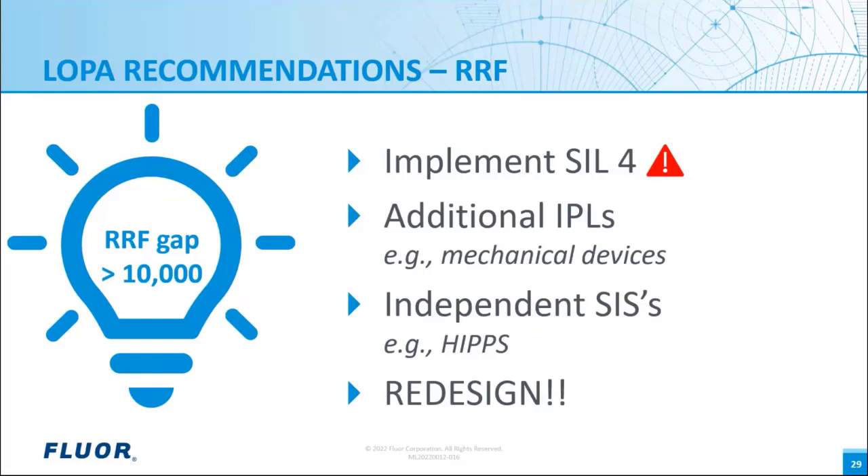For a risk reduction factor up to 10,000, we can apply SIL 1, SIL 2, or SIL 3. If the risk reduction factor is above 10,000, in principle it is possible to implement SIL 4, but this is not common practice for the process industry and is not recommended. We can consider additional independent protection layers like mechanical devices or BPCS functions to reduce the SIL, use an independent safety system like HIPPS, or redesign the process to completely remove the scenario.